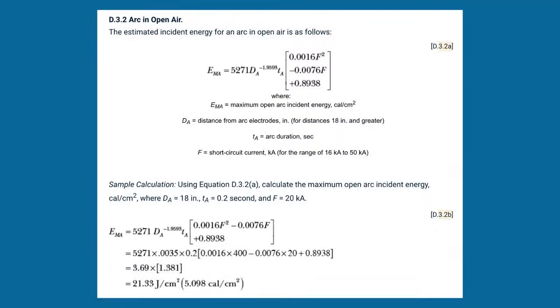But when you're racking something in or out, that distance can be like 24 inches. You see what I'm saying? That will change, so you have to take that into consideration. And then I said, when we get over and look at the tables in a little bit, when you're doing the tables and these calculations, there are two things you need. You need to know what the clearing time is, in other words, how fast it's going to clear in seconds for that arc duration. And you also need to know what? The short circuit current. Now, we were at the service and calculated that in the last one. Now we're going down to a lower level here. Okay. So here's an example calculation right below it.